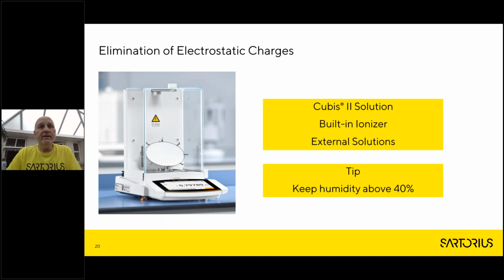How do we deal with this error? Well, we can have anti-static corona introduced into the draft shield to discharge any charge on our tare vessel, and then also on our sample. You can see on this Cubis 2 on this picture on the left-hand side, the 4 points of the ionizer within the draft shield.